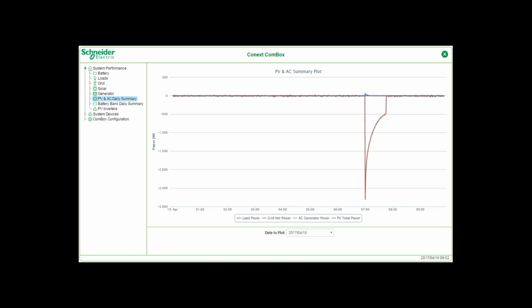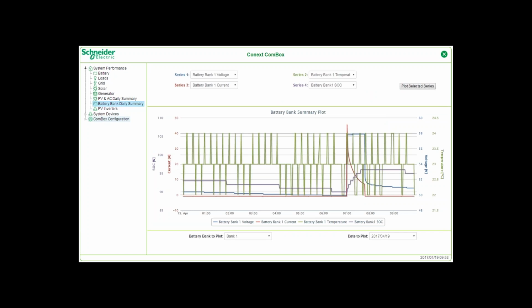PV and AC daily summary provides a snapshot of load watts, grid net watts, generator watts, and total PV watts. So not a lot going on with anything here except for the grid power. We can see the charger ramped up at 7 a.m. and then it gradually tapered off through the absorption stage. Battery bank daily summary provides voltage, current, battery temperature, and state of charge percentage, assuming you have the battery monitor in the network.